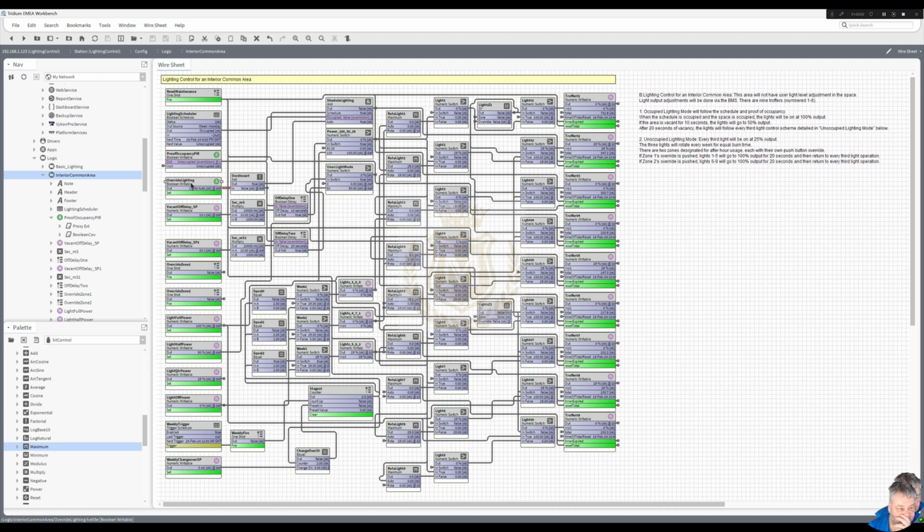They didn't ask for this, for the main override for all of them, but let's do all the lights override. Yeah, they're all 100%. Put that back to normal. Lights on auto. Yep, we've still got the 25% there, 25% there, 25% there. Let's unoccupy.